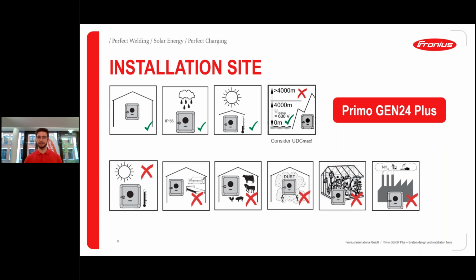Also in a dusty environment, especially when there is metal dust, please make sure to avoid this area. If there is no other place to install it, please also make sure to clean it frequently, like every year or so, to just blow it out so that the cooling ribs are free to distribute the heat again. So this is the most important thing. Glass houses and also factories where there are aggressive chemicals are also no good place to install the inverter.